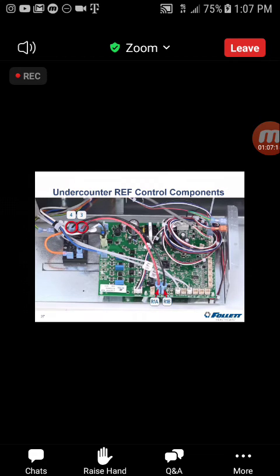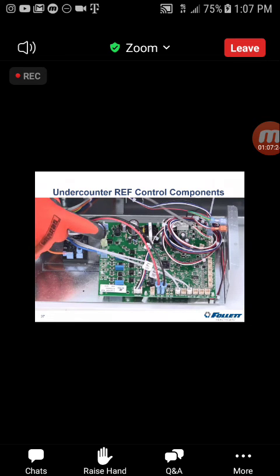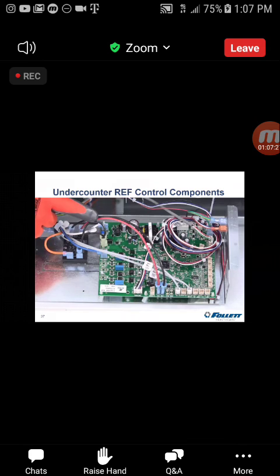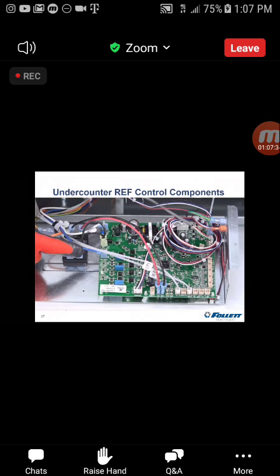If the wires are accidentally misconnected, the relay will not be damaged. However, it will be inoperative. The system will not run. The power comes through the power switch, goes through the black wire to the L1 terminal on the control board, where a jumper wire brings power to the power side of the contacts of the relay. The load side has the orange wire that goes over to the compressor and to the condenser fan motor. On the right-hand side of the board, we can see 3 connections grouped together. This is where the communication cable coming from the user interface is connected to the board. All 3 of these are like USB ports. They all do the same thing. That connection can go to any one of those 3 connectors.